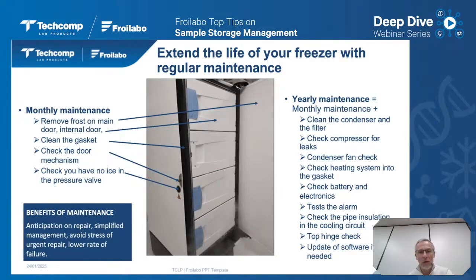The yearly maintenance is often offered by Froilabo or by partners of Froilabo, to have a complete check of the unit. We will check the condenser and the heat exchanger of the unit. We will check how the compressor is working. We will check the fan. We will check plenty of different things. And at the end, we will be able to know if the equipment is working as expected, and sometimes we are able to identify if we have to anticipate a repair. It's very important in terms of the management of ultra low temperature freezers.